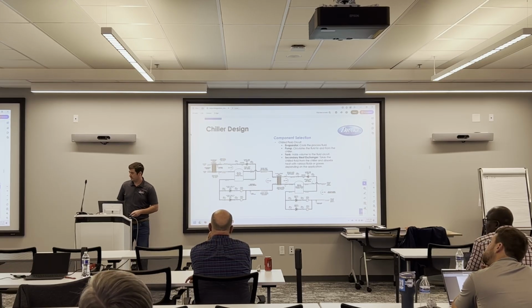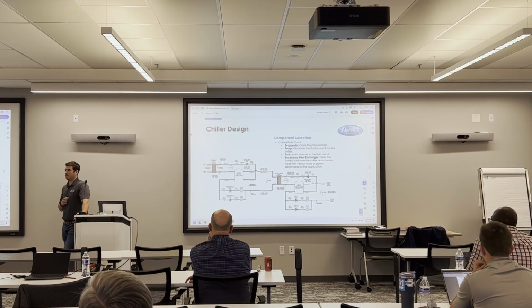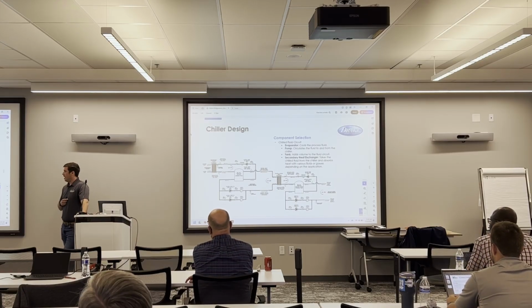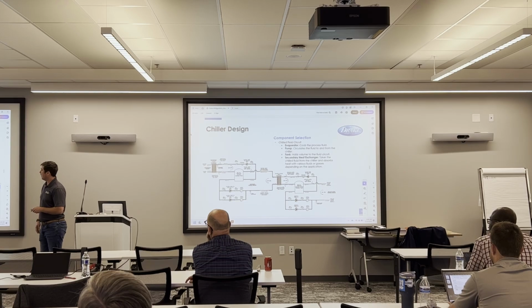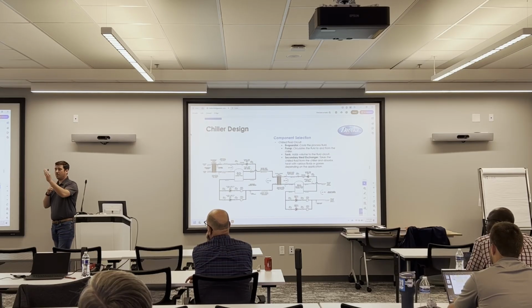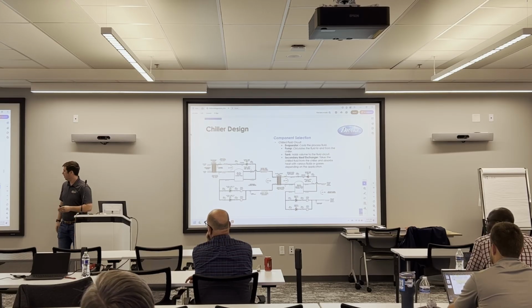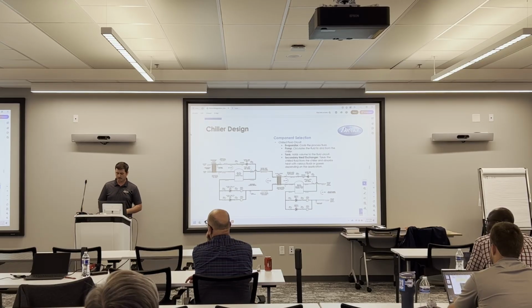Is there any difference if you want to put it on the water process or level water? Yeah, so there's certain rules and regulations you need to adhere to. If you're going to be doing potable water, you can't run that through a normal braze plate because it's not sanitary. So you can either do a secondary heat exchanger setup like this, where you have glycol on one side and water on the other. If you have 2 degrees of separation from the refrigeration circuit, this would be a sanitary grade setup, because there's no way the water's going to mix with the refrigerant because there's too many heat exchangers. Or you can do that potable braze plate that we talked about, where you have that thin wall. It's not possible for the refrigerant to mix in with the glycol if you have a failure, because there's just an empty space there. Yep. There's a bunch of different ways you can mitigate that.